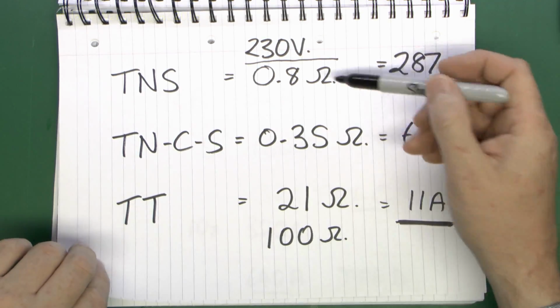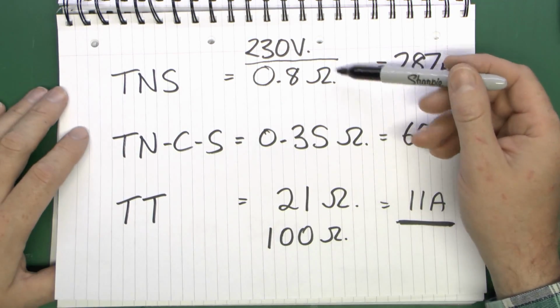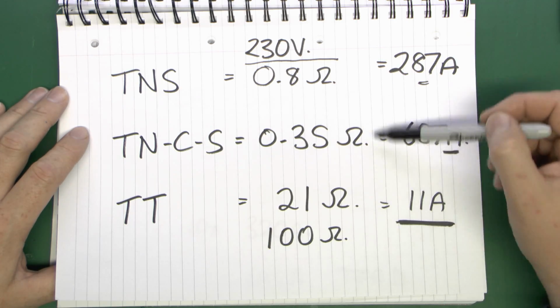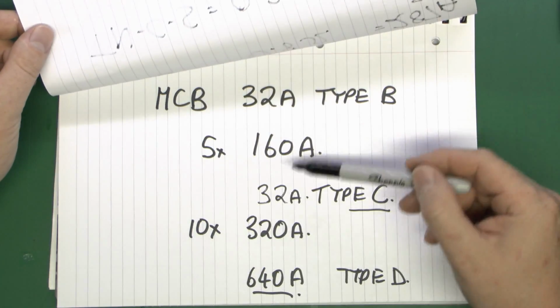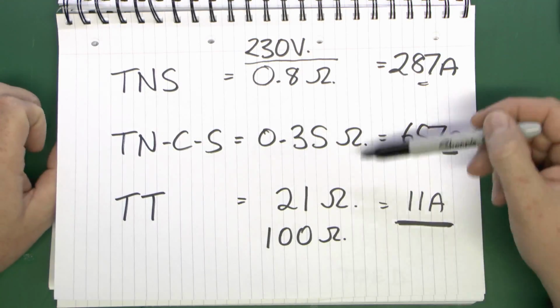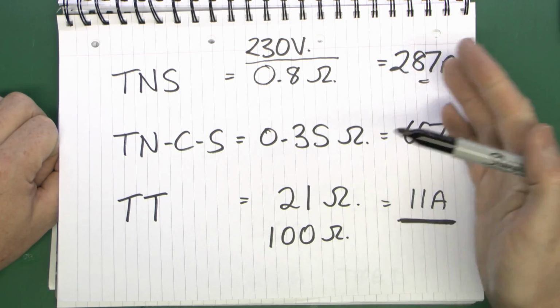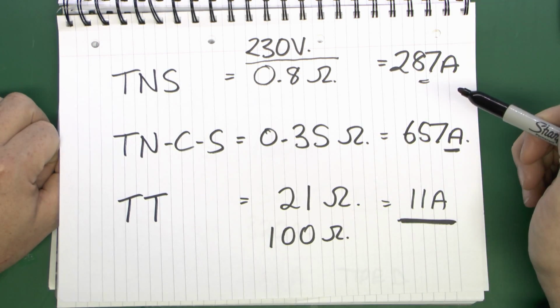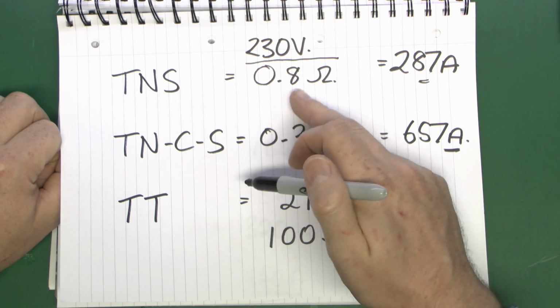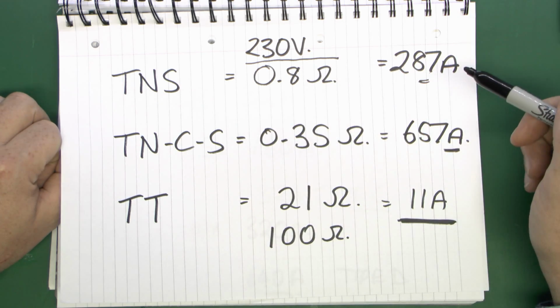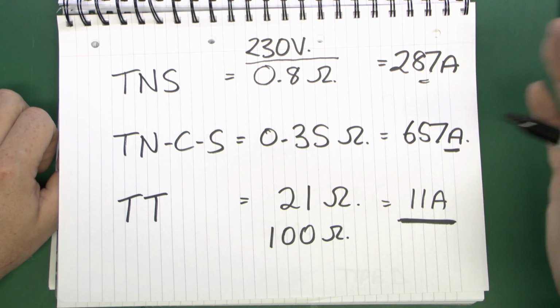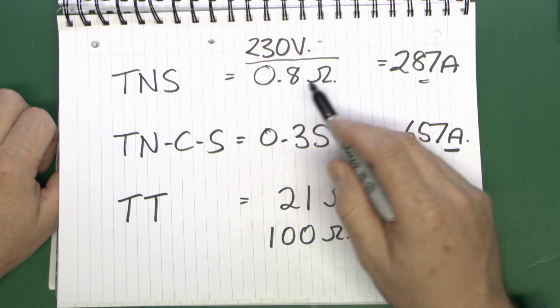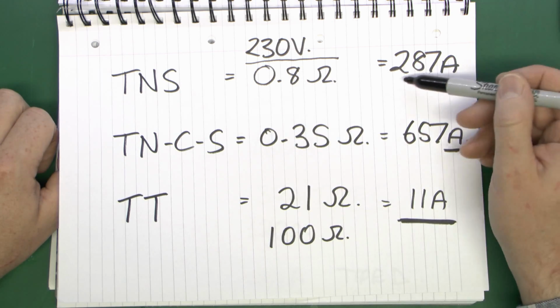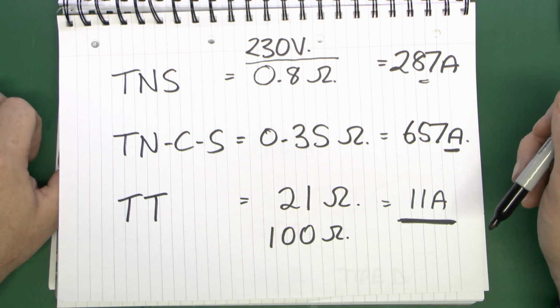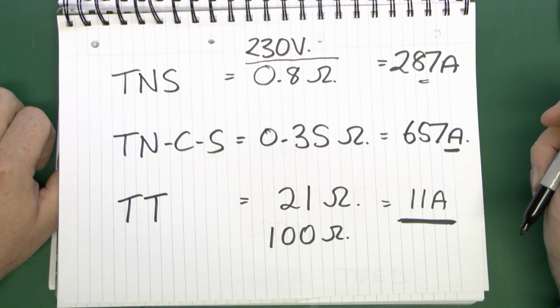Now, something else to consider here as well, this is just talking about the external impedance, so literally the supply as it comes into the building. But in a real situation with circuits, it's not just the external impedance, you also have to add on any impedance for the circuit wiring itself. So it's 0.8 in this case, plus whatever the resistance of the cabling is. And if you've got particularly long circuits, that can add quite a significant amount to these, and again reducing the available current here in the event of fault even further.